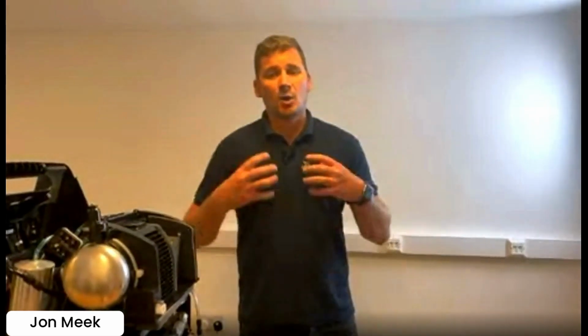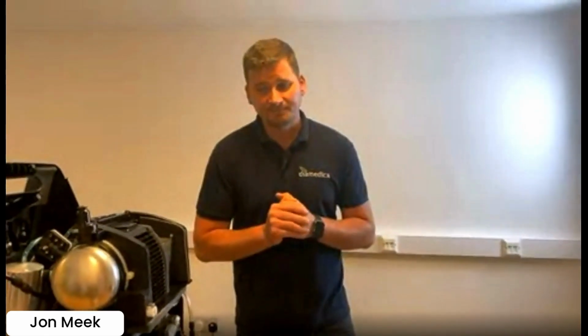Sure. Over to you. Yeah, absolutely. So the humidifier bottle is warmed. You can't use, or you can use but you shouldn't use, cold water. You want to warm the humidifier bottle because that adds humidification for the infant. The colder the bottle, the less humidification is going to come from that bottle, or the less oxygen is going to be humidified. So we warm it to a certain temperature to allow about 80% humidification, depending on local temperature, but it's adding humidification, which is really important. If you don't warm it, you're not going to add extra humidification. You'll be adding very little into the machine.